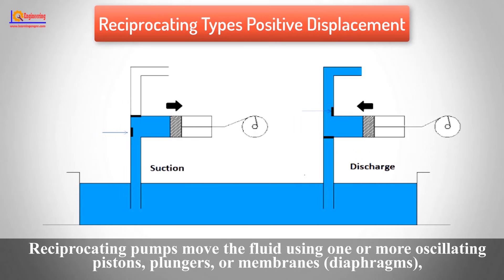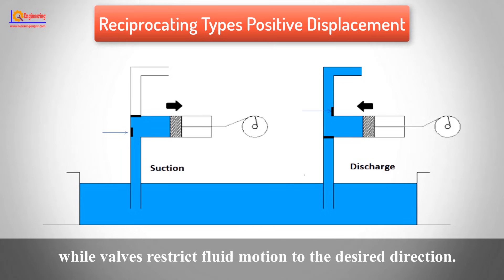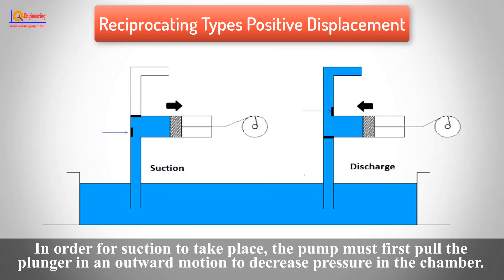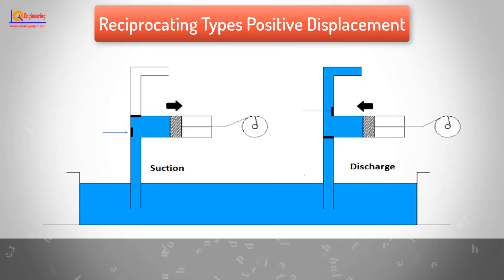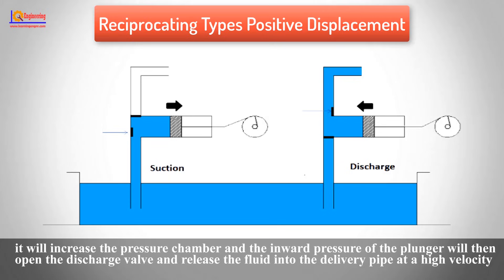Reciprocating Type Positive Displacement Pumps move the fluid using one or more oscillating pistons, plungers, or membranes, while valves restrict fluid motion to the desired direction. In order for suction to take place, the pump must first pull the plunger in an outward motion to decrease pressure in the chamber. Once the plunger pushes back, it increases the pressure in the chamber and the inward pressure of the plunger opens the discharge valve, releasing the fluid into the delivery pipe at high velocity.